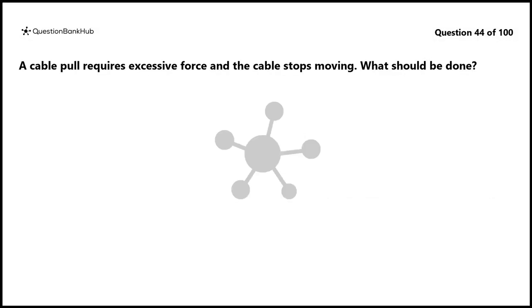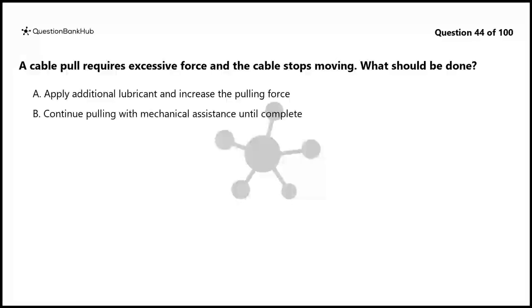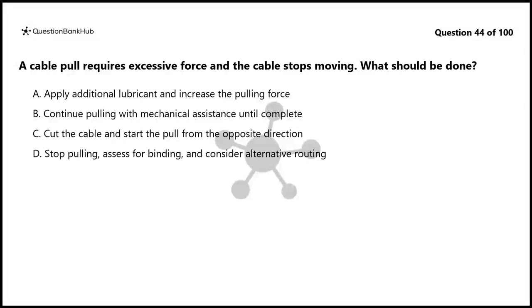Question 44. A cable pull requires excessive force and the cable stops moving. What should be done? A. Apply additional lubricant and increase the pulling force. B. Continue pulling with mechanical assistance until complete. C. Cut the cable and start the pull from the opposite direction. D. Stop pulling, assess for binding, and consider alternative routing.